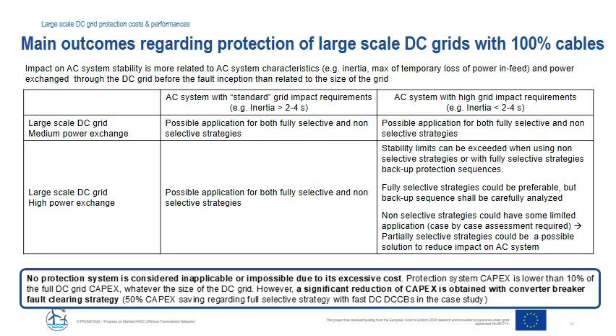No protection system is considered inapplicable or impossible due to its excessive cost. Protection system capex is lower than 10% of the full DC grid capex, whatever the size of the DC grid. However, a significant reduction of capex is obtained with the non-selective converter breaker fault clearing strategy. It appears that there is no single preferred protection strategy which outperforms all other protection strategies. It is more a question of finding the best techno-economic option among all proposed protection strategies, considering both required performance and cost. As such, it is a real benefit to have the opportunity to select very different options for protecting DC grids.